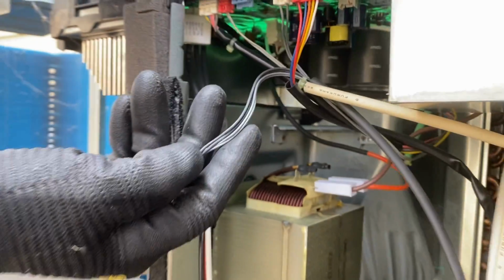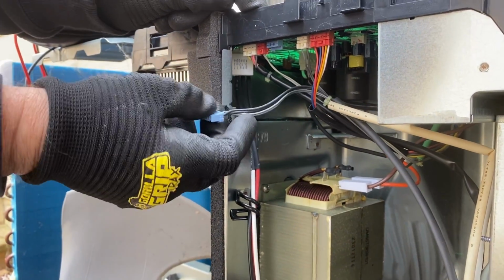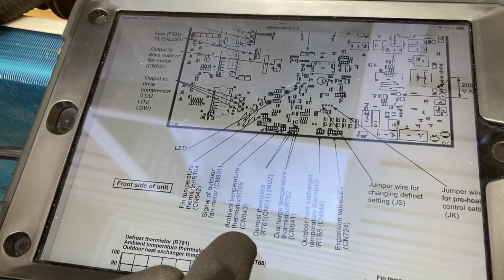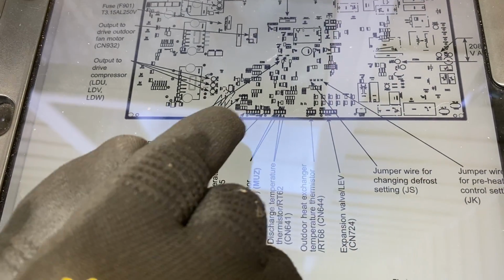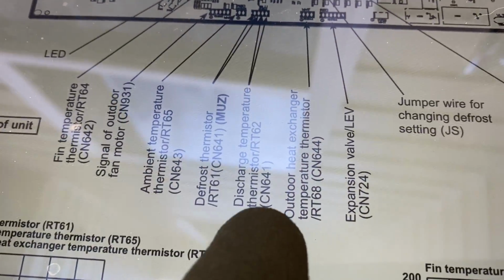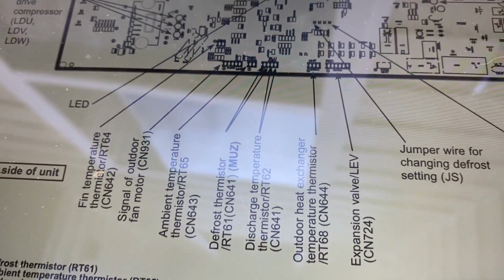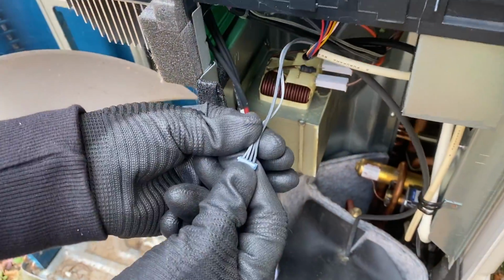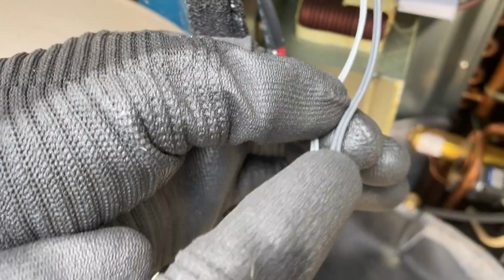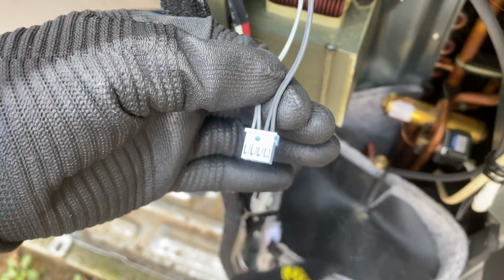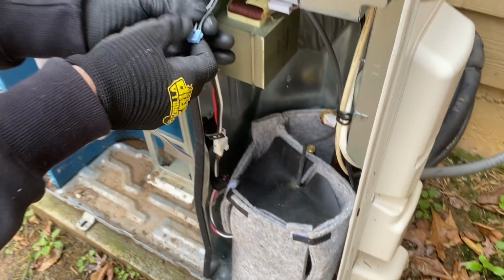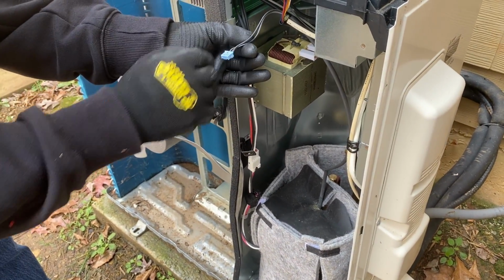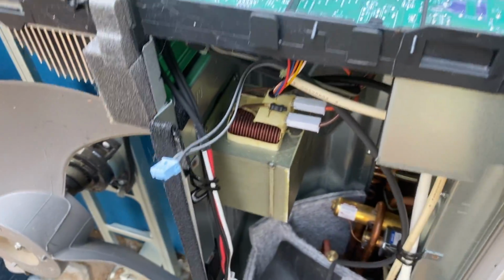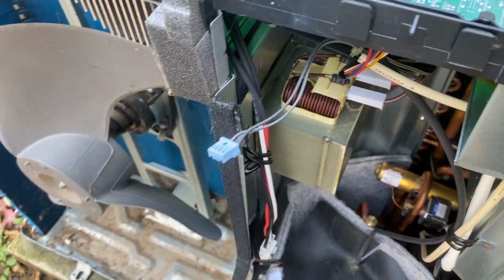Now there's two different thermistors right here, and how do I know which one is which? We go back up to the test point diagram, and we see that your defrost temperature thermistor is on the left hand side there, and over here your discharge temperature thermistor is right here. So the two black wires right there would be your discharge temperature thermistor coming from the compressor, and this would be your defrost temperature thermistor coming from the coil. But that's how you would know.